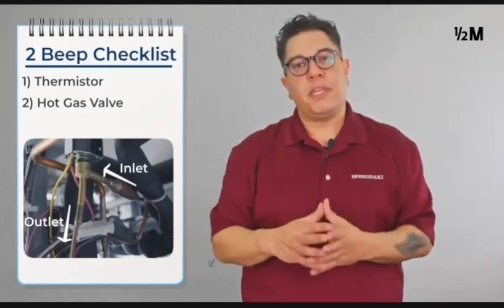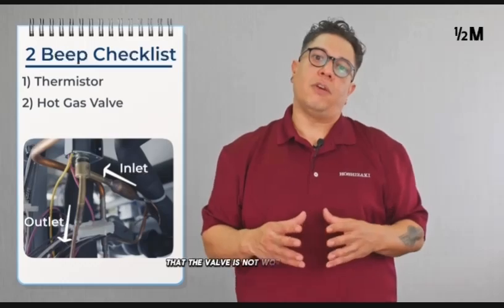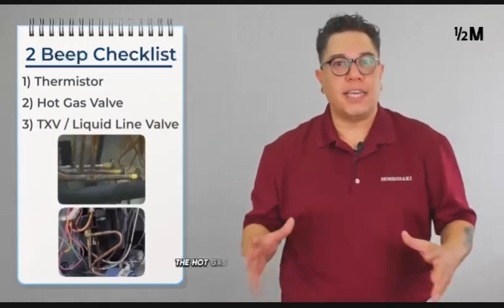If we have a bigger split, there is a possibility that the valve is not working properly, and it might need to be replaced. Once we confirm that the hot gas valve is not leaking by, then we can move on to the next step.